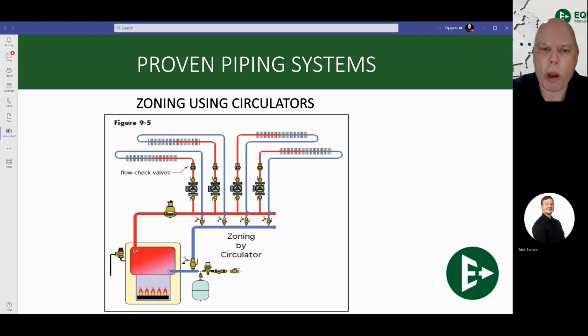But it has its drawbacks as well, where using this many pumps can be a little bit expensive, and you've got to know your piping size correctly, where you're going to have a 1.25 inch main and maybe 3/4 inch pipe sizing going into each individual zone. It does work very well. It's easy to zone, but there are more advanced ways to do it nowadays. But this one here, you're almost guaranteed to see out in the field starting right now.